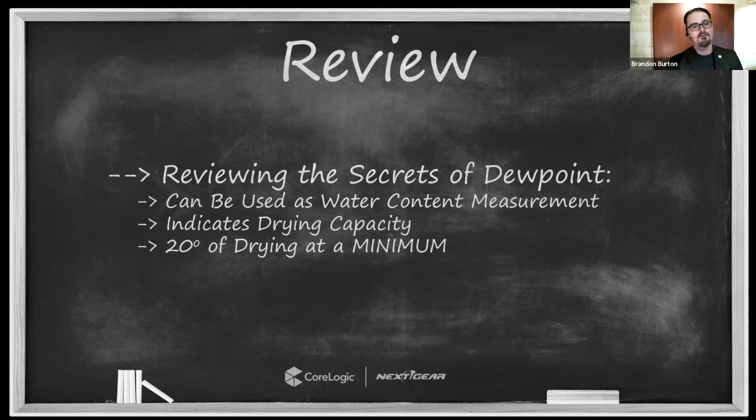If you've attended previous Technically Speaking episodes, we ran through a formula on that. CFM times grain depression divided by 71, you may remember. And that calculates pints of water removal. In that case, I really need grains.